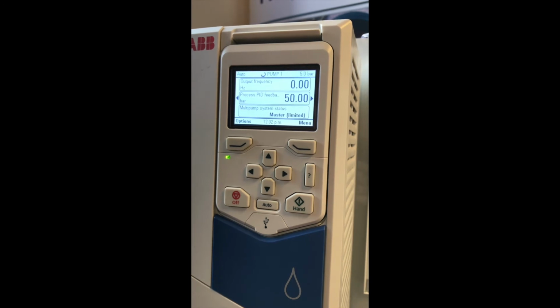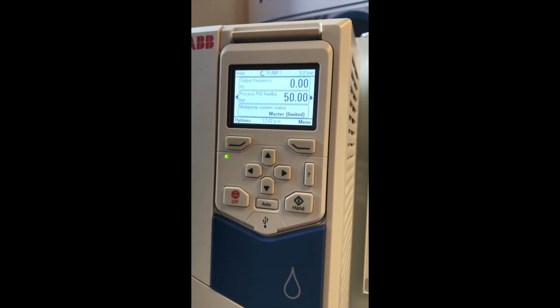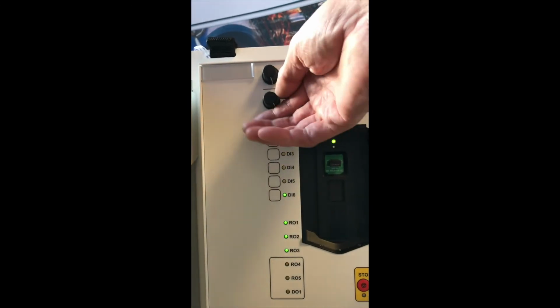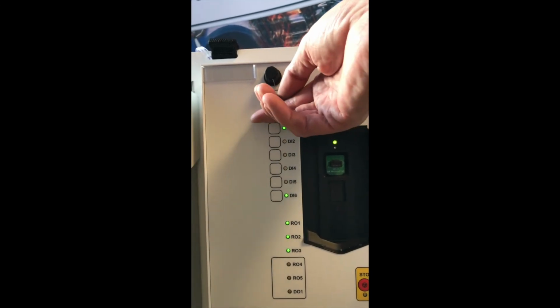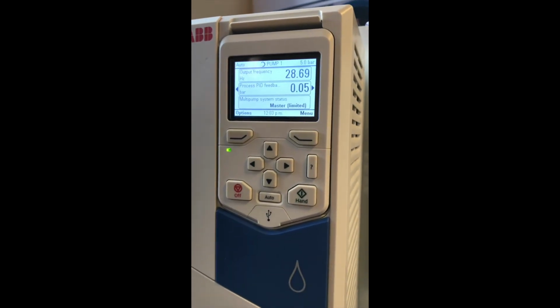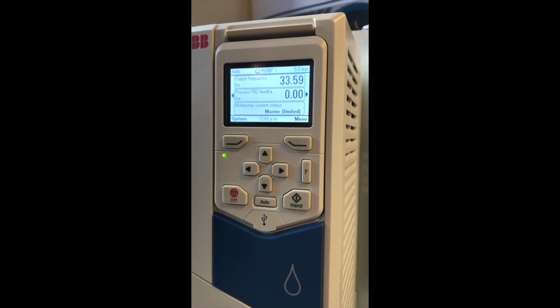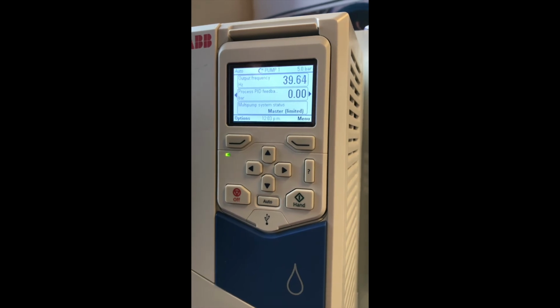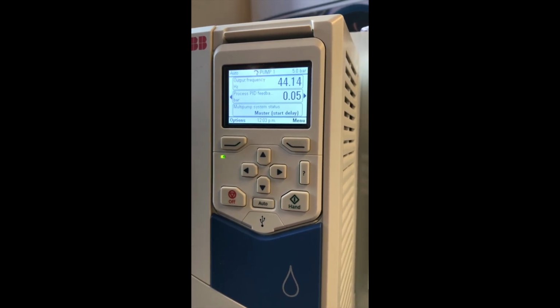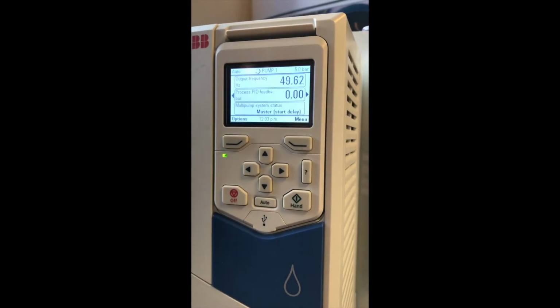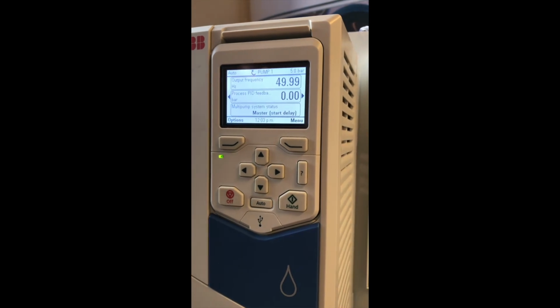Pump 1 is the master. The feedback is set up by analog input 2, which I'm now going to reduce to represent a drop in pressure. Pump 1 will accelerate up to try and compensate and meet the demand. When the pump reaches the set point that we've put in the system and the demand is not met, pump 2 will automatically be called in to assist.